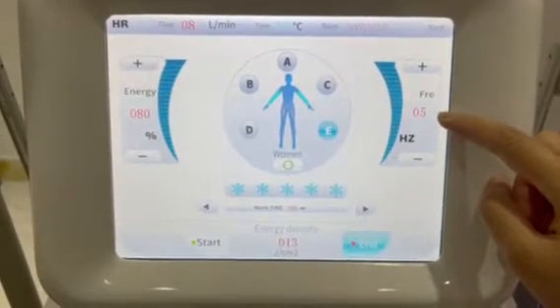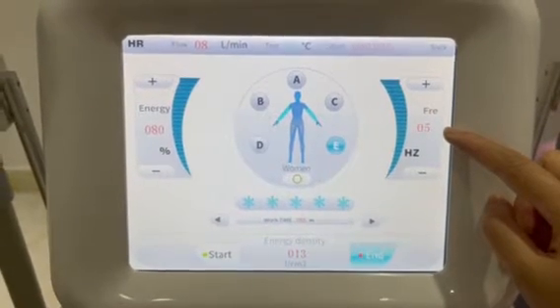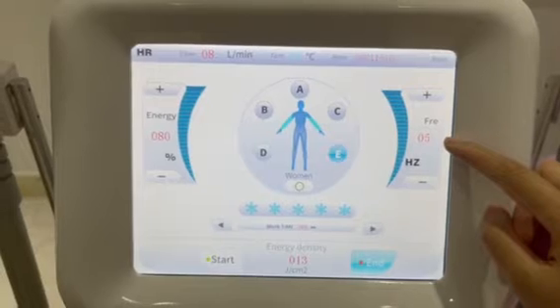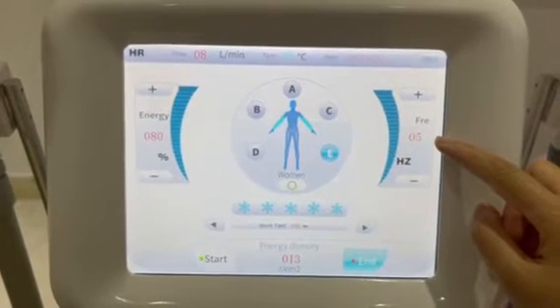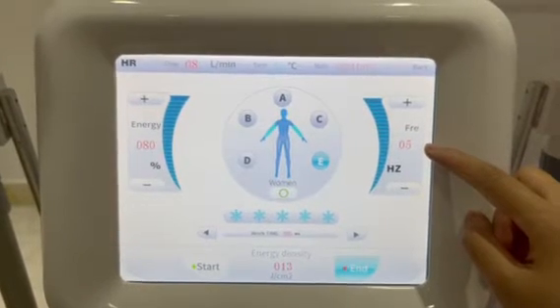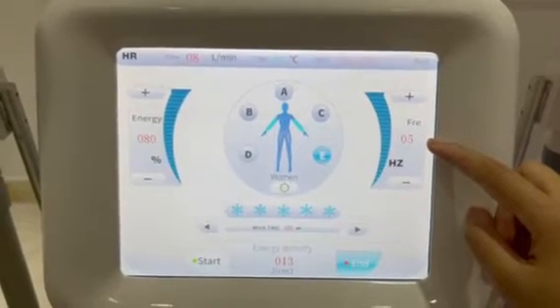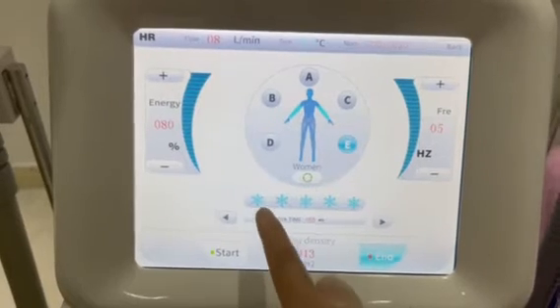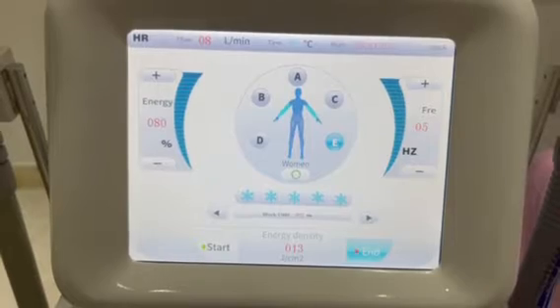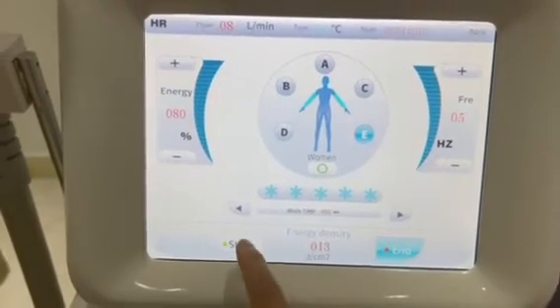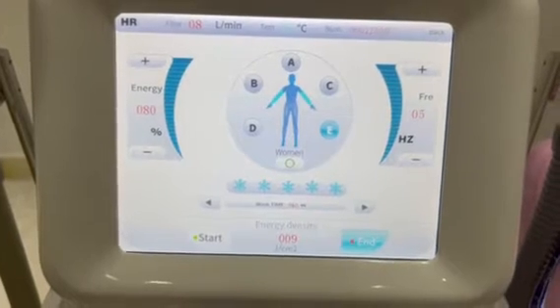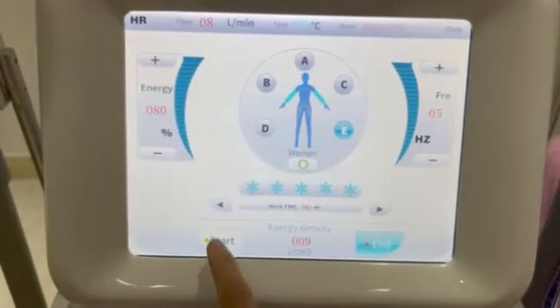Frequency is the speed of shots. For small part treatment, we advise you start from frequency 2. If you do hair removal for the leg and arm, we advise frequency 4 to 6. Cooling level has 5 grades; we advise you switch to cooling level 2. Work time — advise 40. Then press start.